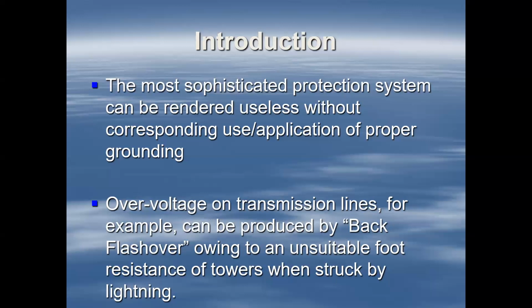But for that particular pole, there's a wooden structure at the side where they use a little metal covering through which the earthing wire goes. When we went to the top of the wire, we were reading 700 and odd ohms. So at the bottom we got nice, beautiful readings, but a little higher up, we got 700 and odd.